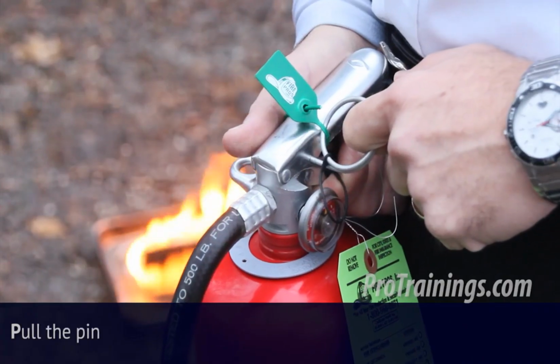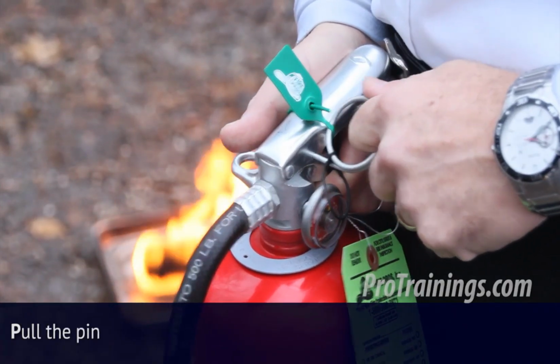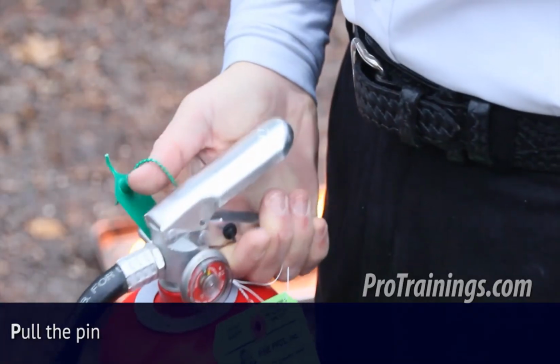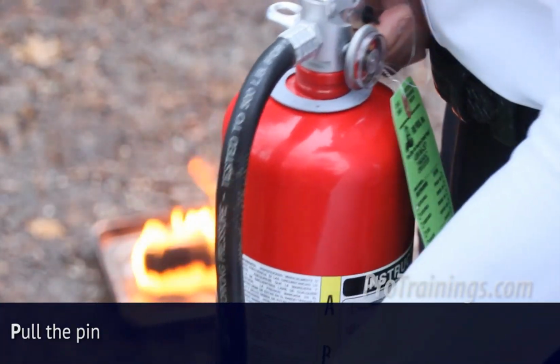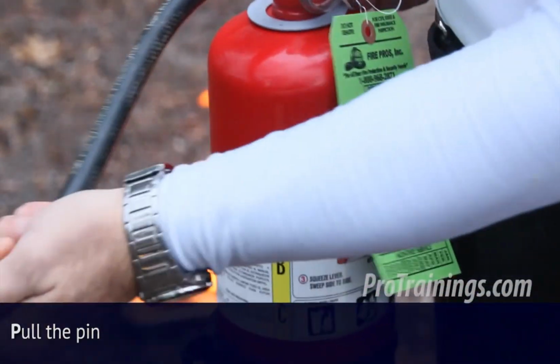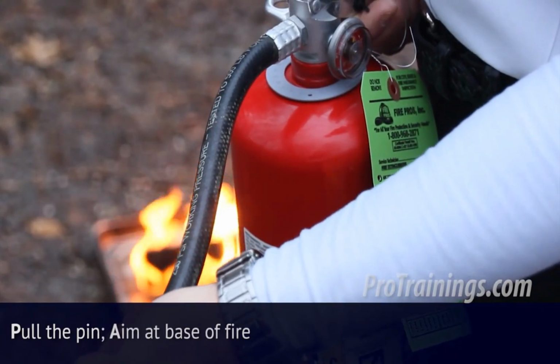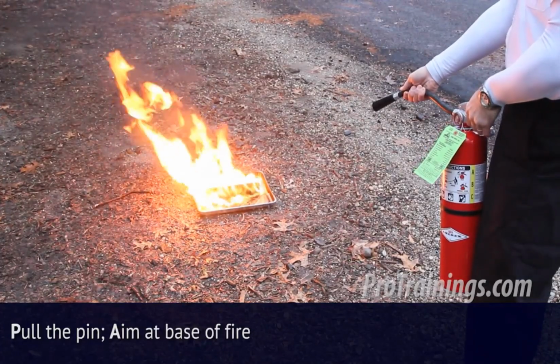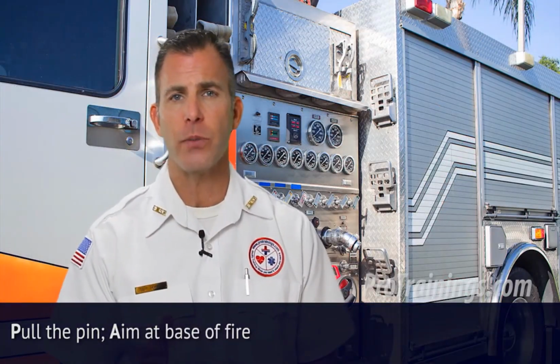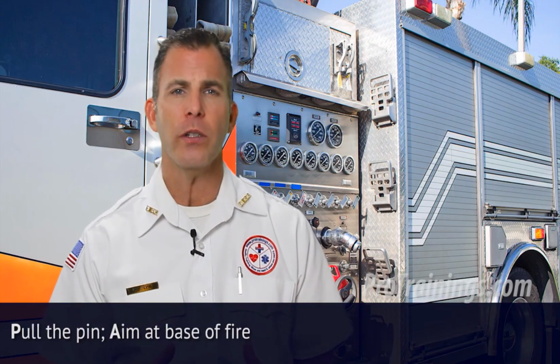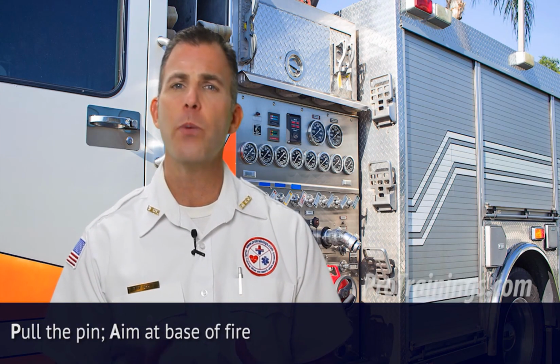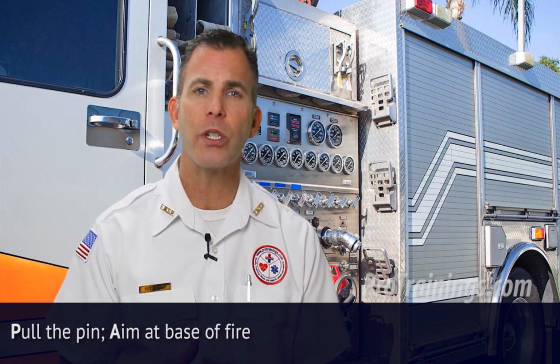As a general rule, it helps to remember the acronym PASS when using an extinguisher. P is for pull the pin at the top of the extinguisher. The pin releases a locking mechanism and will allow you to discharge the extinguisher. A stands for aim. Aim at the base of the fire, not the flames. This is really important in order to put out the fire. You must extinguish the fuel in which the fire is coming from.